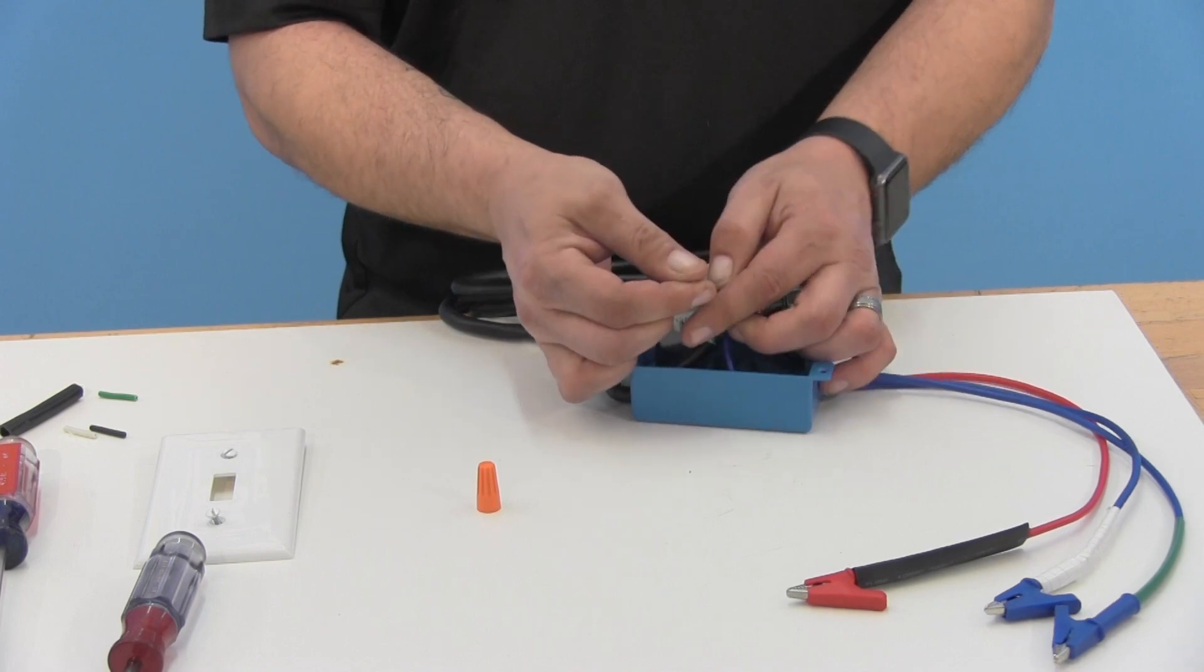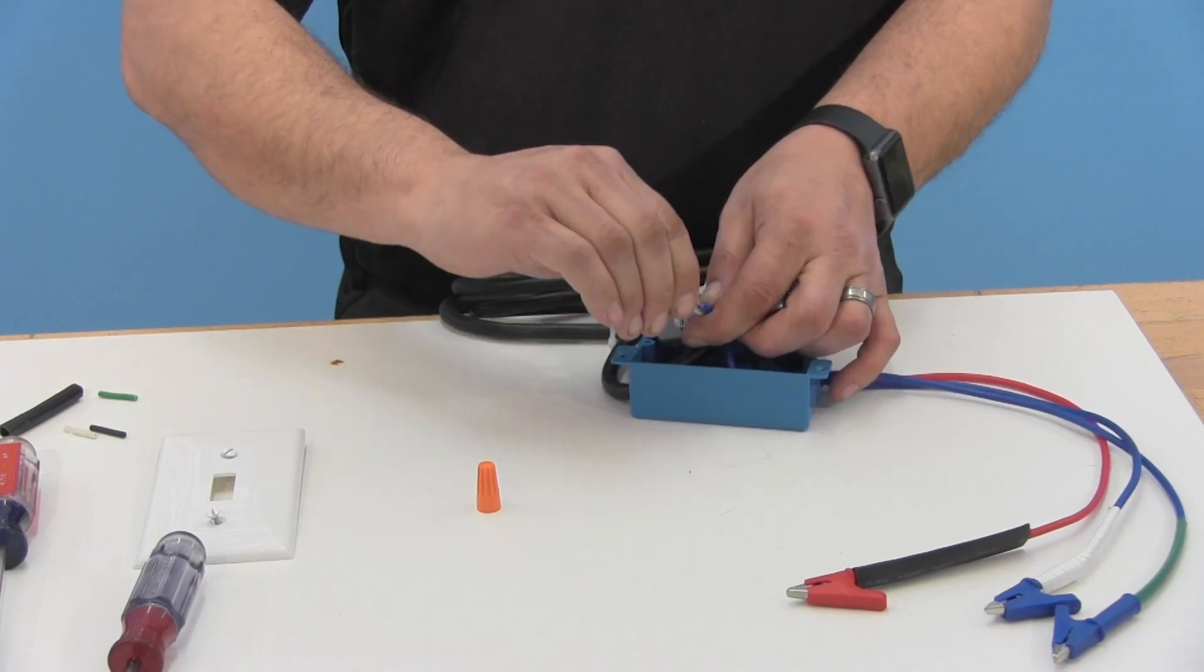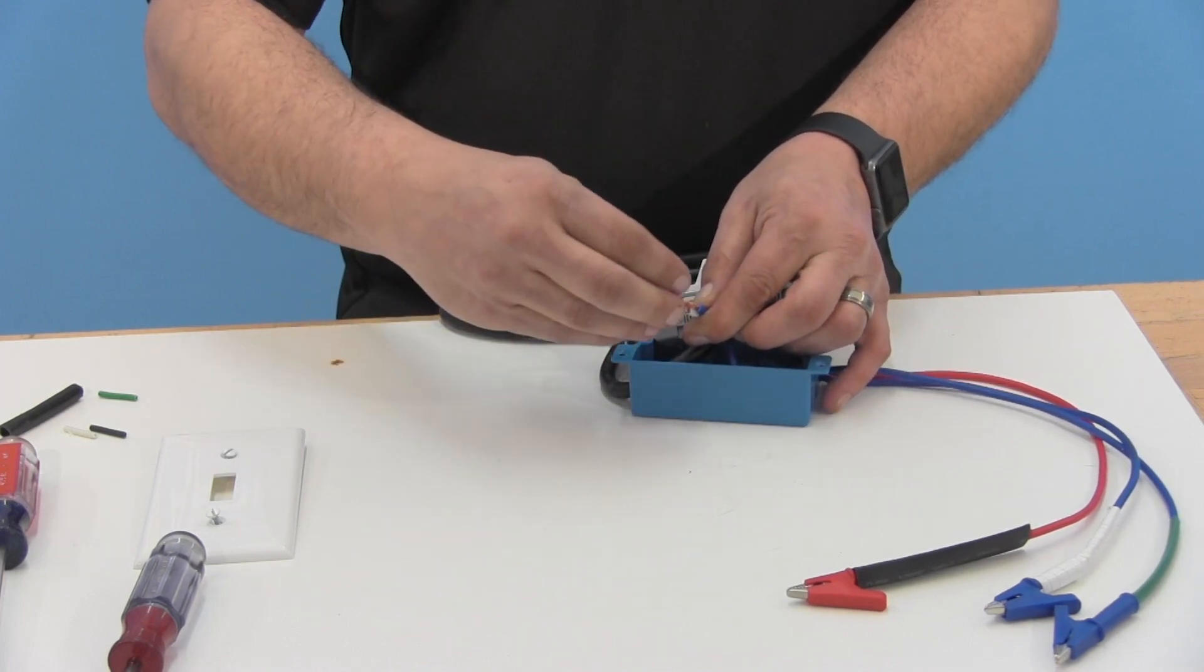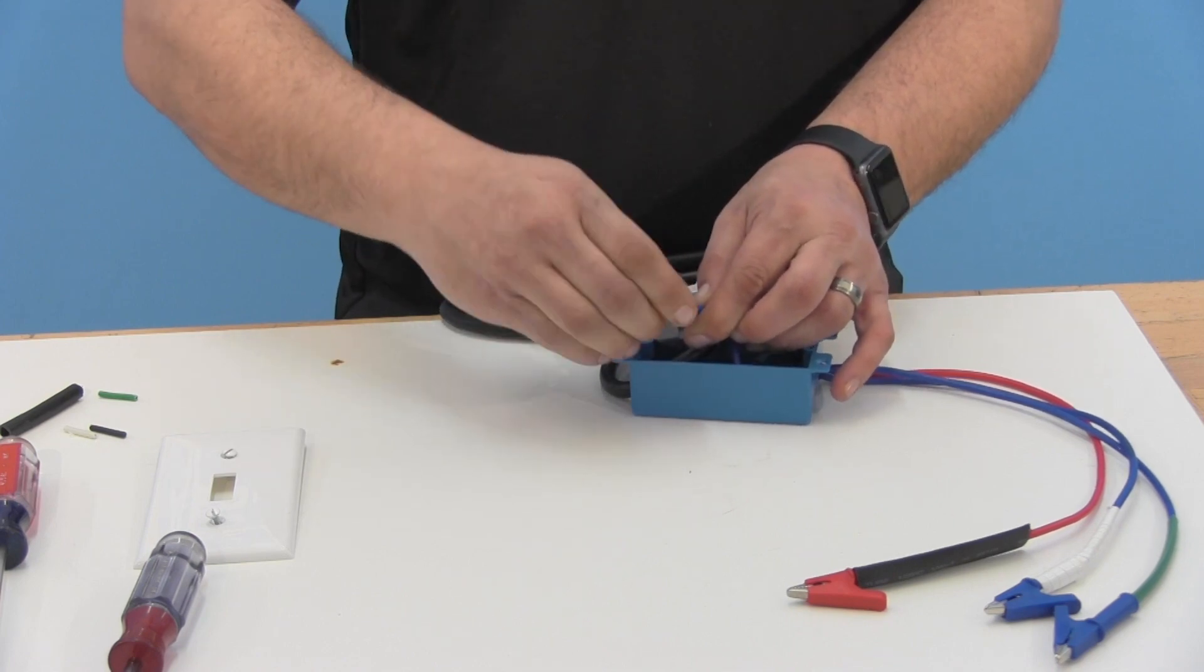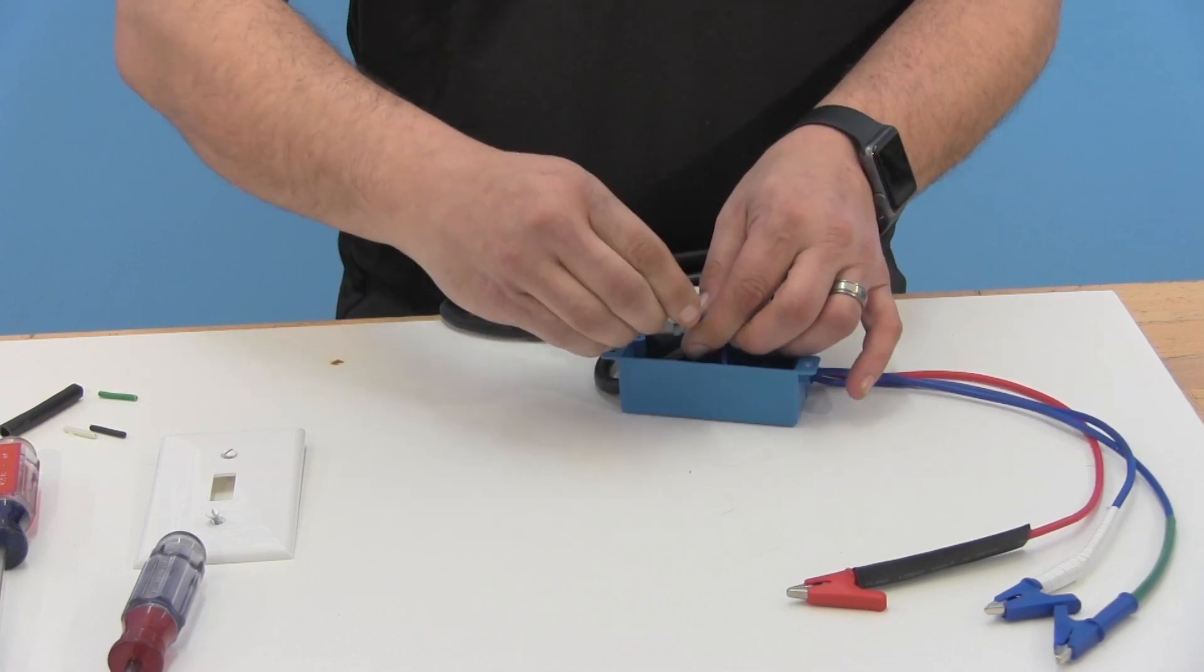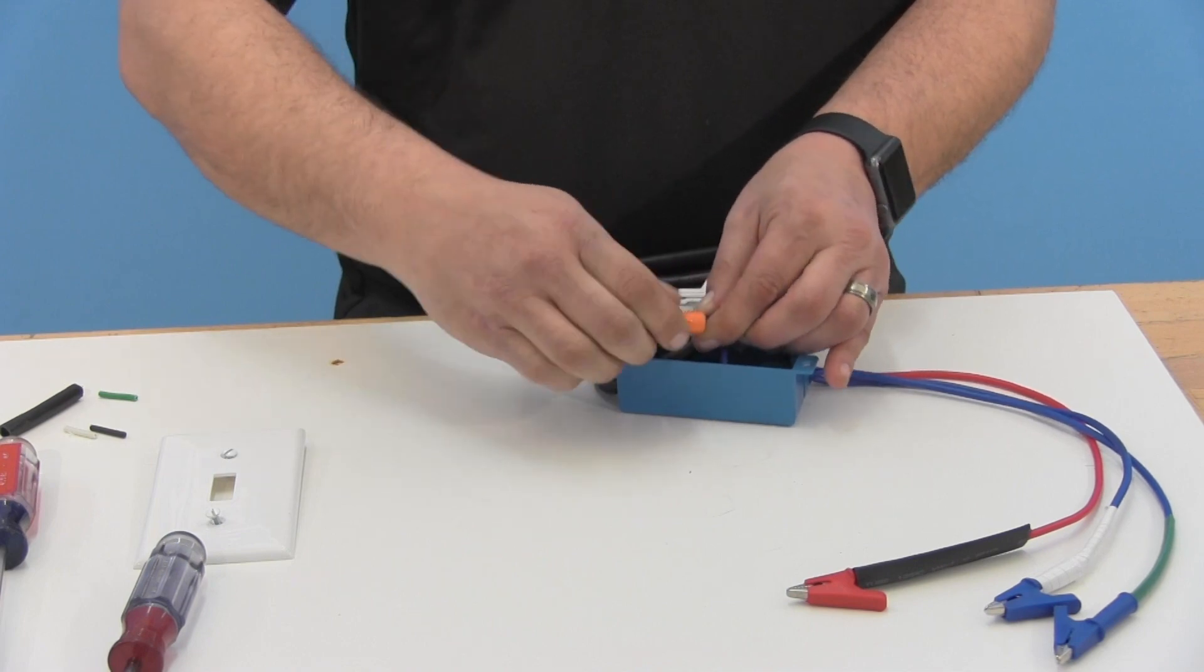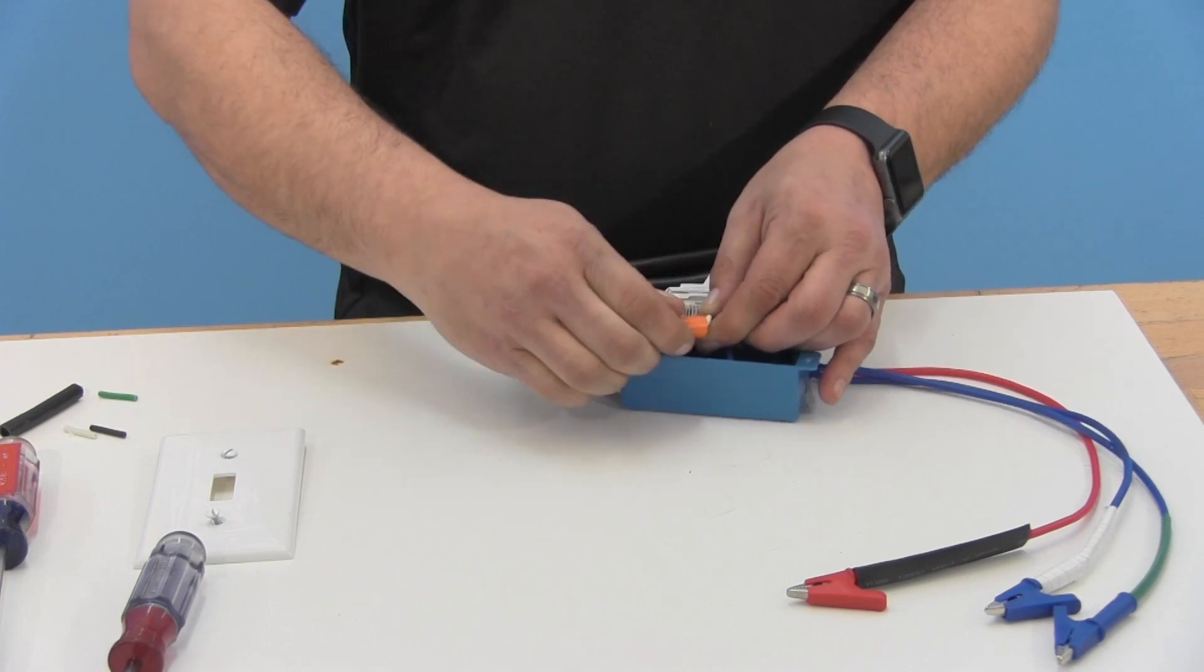Don't twist these wires together, just simply place them next to each other. Using a wire nut, go ahead and screw that wire nut down and the wires should actually start to twist on their own. That kind of indicates that they're braiding together.